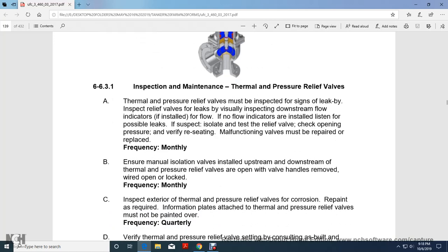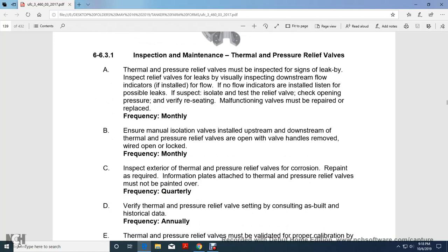Inspection of thermal pressure relief valves. Thermal pressure relief valves must be inspected for leaks at the time of inspection, checking downstream of the relief valve for leaks and flow indicators if installed. If flow indicators are not installed and a leak is suspected, isolate the relief, check the opening pressure of the relief, and verify reseating. A malfunctioning valve must be repaired or replaced frequently.